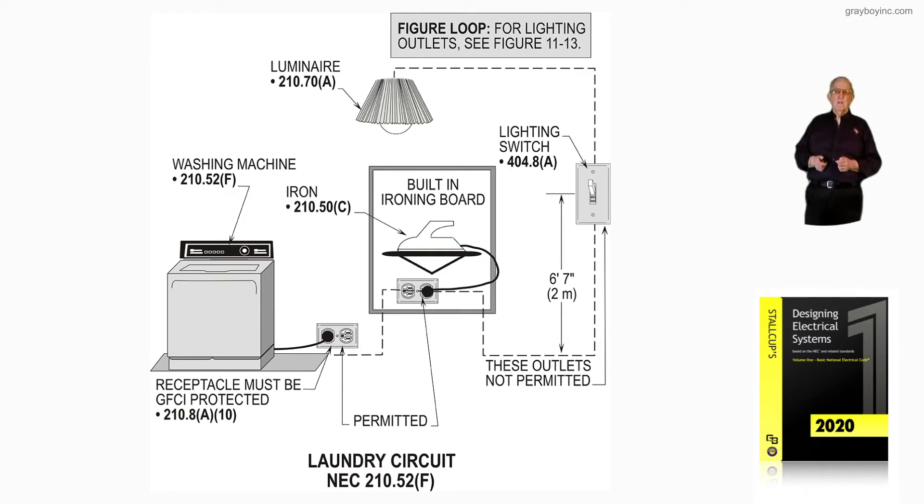Notice we could not supply a lighting outlet — the one you see there — with this laundry circuit via a switch switching the luminaire, per 210.70(A). However, this circuit in accordance with 210.50C could supply a laundry circuit outlet for, say, a pull-down ironing board with a receptacle for the iron.